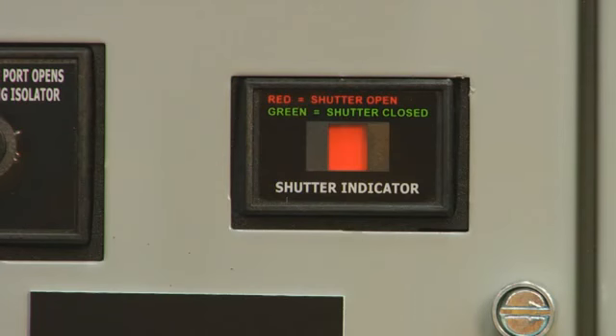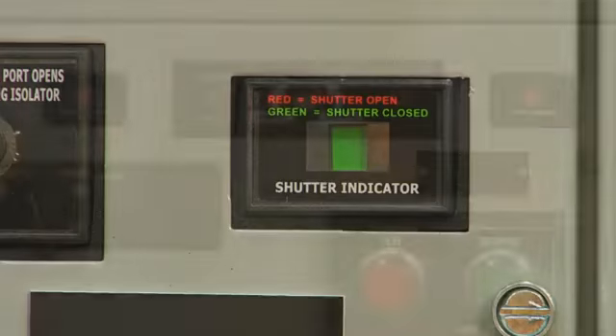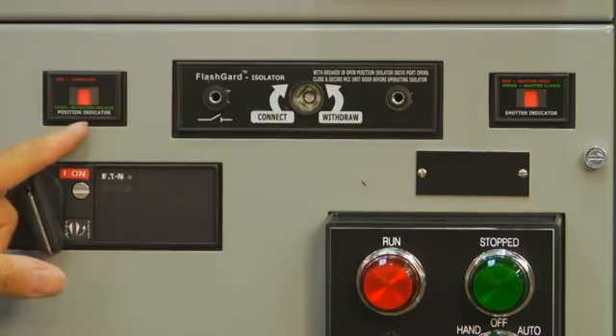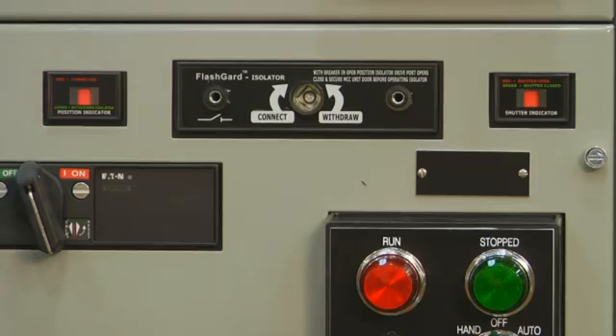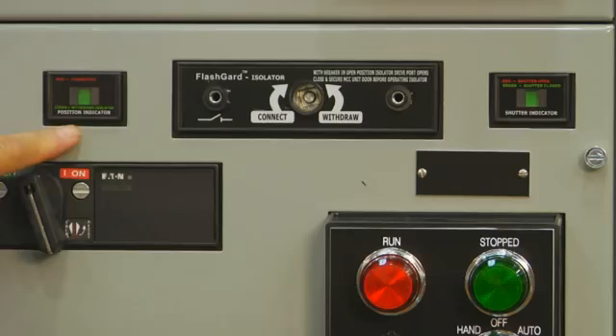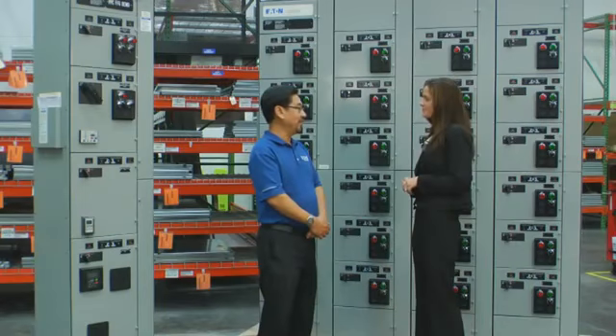A red indicator means that the stabs are connected to the vertical bus and hazardous voltages are present and being delivered to the FlashGard unit. A green indicator means that the stabs have been withdrawn and the unit is now in an isolated mode. In other words, the stabs have been disconnected from the vertical bus and hazardous voltages are no longer being delivered to the FlashGard unit. Separately, the shutter position indicator provides further verification of the bucket's safety status by indicating whether the internal isolation shutters are open or closed. These shutters will only close when the stabs have been fully retracted within the FlashGard unit and disconnected from the vertical bus.